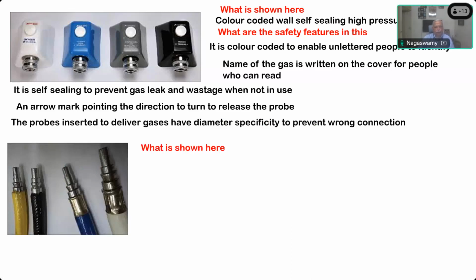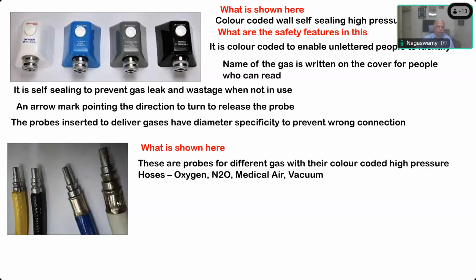Now, what is shown here? Color coded high pressure hoses. They are called hoses, not hose pipes, but high pressure hoses. These are probes actually, and most of them are showing the probes so that you can identify the different diameters here. The probe tip goes in here, and then it will get locked only at the particular outlet. So the white one will go only into oxygen. The blue one can be fitted only to nitrous oxide. You cannot insert the other one because the diameter here at the neck will be varying. So it will not fit into the improper outlet. So these are probes for different gases with their color coded high pressure hoses, namely oxygen, nitrous oxide, medical air, and vacuum. Which one is the vacuum here?